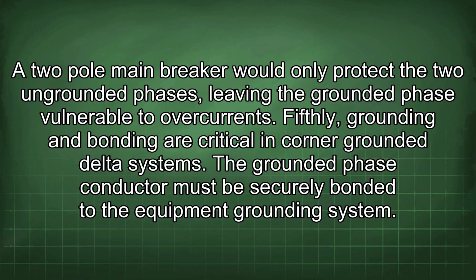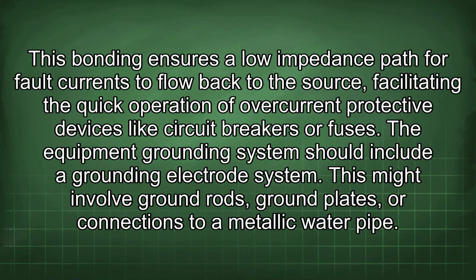Fifthly, grounding and bonding are critical in corner-grounded delta systems. The grounded phase conductor must be securely bonded to the equipment grounding system. This bonding ensures a low impedance path for fault currents to flow back to the source, facilitating the quick operation of overcurrent protective devices like circuit breakers or fuses. The equipment grounding system should include a grounding electrode system.